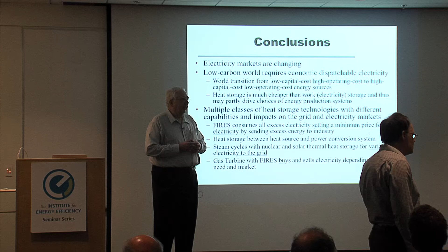It turns out that some other people, by the name of General Electric, have been working on this problem. They have a project that's now on hold because of changes in price structures in Germany. This is a project with RWE, the German utility, where they're looking at adiabatic compressed air storage. What you do is take air, compress it to about 600°C and 70 bar, run it through a recuperator in a pressure vessel, and inject the compressed air underground into a salt cavern for storage. The compressed air goes through a recuperator because you can't have 600°C hot air down in your salt cavern — it would begin to fall apart from the high temperatures. To discharge this storage device, the compressed air comes up, goes through the brick recuperator, gets reheated, and heads out to the gas turbine for peak power production.